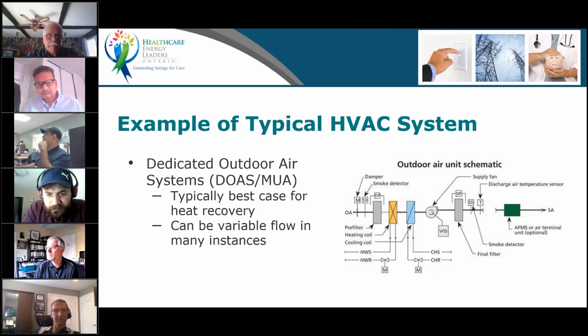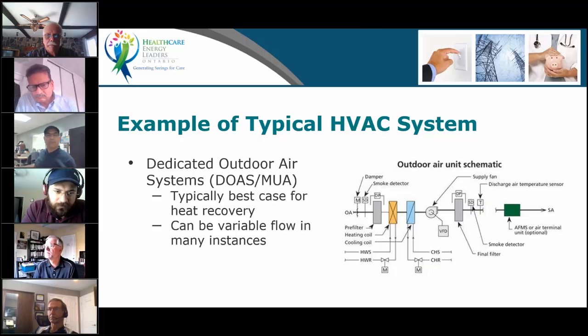Another one that's very common is a makeup air unit. It's 100% fresh air. Older design in healthcare had a lot of makeup air units for, let's say, operating rooms or even for the patient care section, where all you had was a makeup air unit feeding corridors or feeding the actual spaces, the rooms themselves. Those are perfect for heat recovery. They are the best candidate for heat recovery when it's possible, obviously. If you have many exhausts, that becomes impossible. You have to have centralized exhaust.